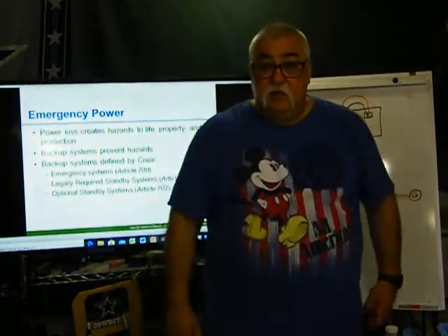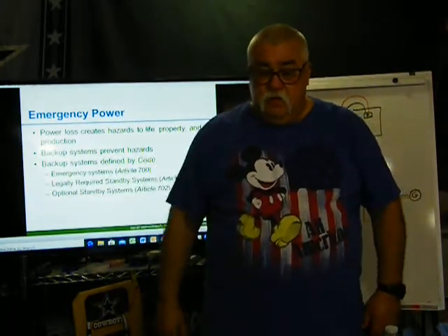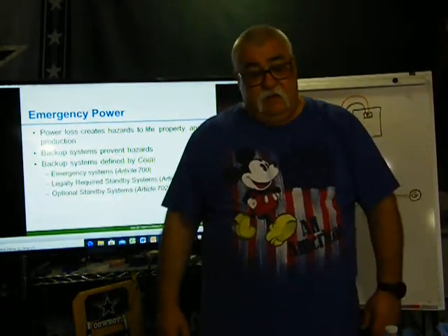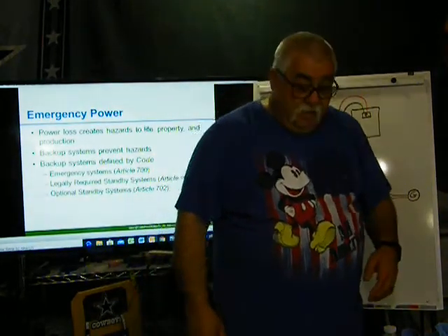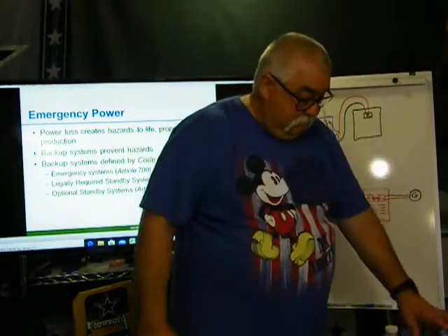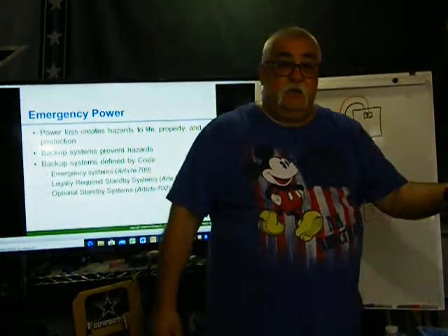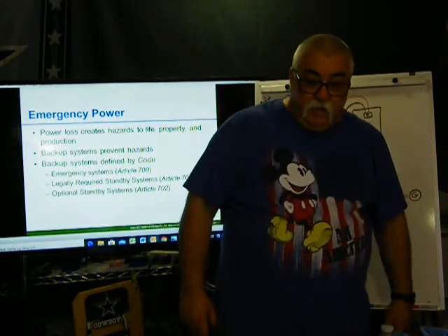I said, man, it's going to be a big generator. We're going to have to put it out there in the parking lot. We're going to have to dig across the street. He goes, oh, no, I want it right next to here. And I said, hey, guess what? It ain't going to work. You put it right next to here, forget it. Ain't nobody going to be here. You can run the generator, but nobody is ever going to do anything because it's so loud. He thought it was going to be a small generator you can put in, and he can run his business. It's not the way it works.